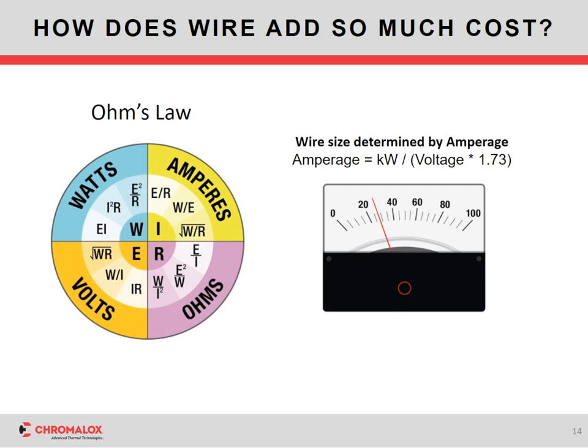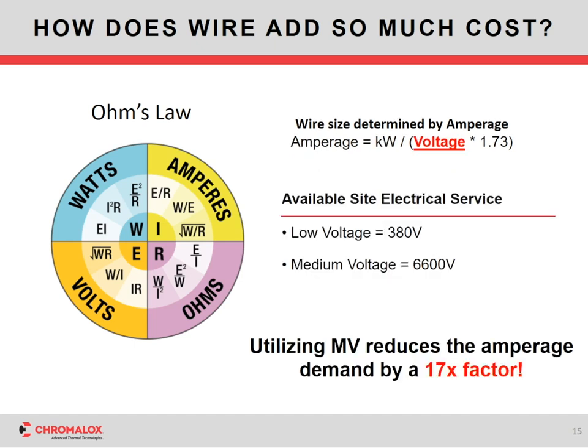Okay, so if we just take a minute and ask, why does a low voltage system add so much more cost than a medium voltage system? That really goes back to Ohm's law. We need to determine the amperage for such a system, because amperage is really the kilowatts, or the heating load, divided by the voltage.